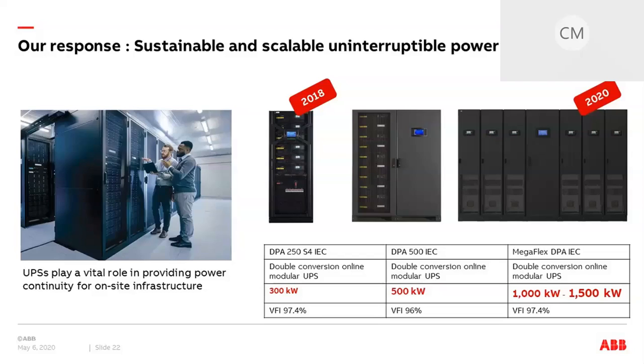For mid and high power infrastructures, we present the DPA 500 UPS, which offers in a single system up to 500 kilowatts and is based on power modules of 100 kilowatts. For large enterprises and colocations, the new MegaFlex DPA with rated power of 1 megawatt to 1.5 megawatts is based on power modules of 250 kilowatts. The new UPS was launched in March this year at Data Center World London, presenting and validating the best-in-class efficiency with the smallest footprint.